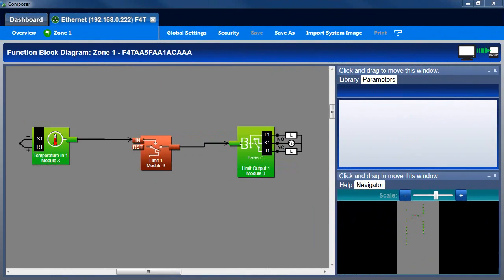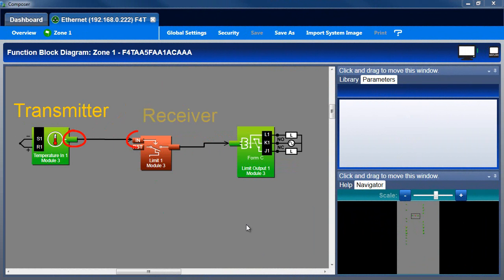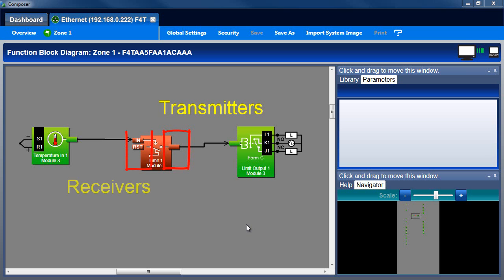The controller is configured for an application by connecting signals between blocks on the canvas. A signal carries data from a transmitter on the right side of one block to a receiver on the left side of another block. Connections on the right side of a function block transmit data for use by other blocks. Connections on the left side receive data for use by that block.